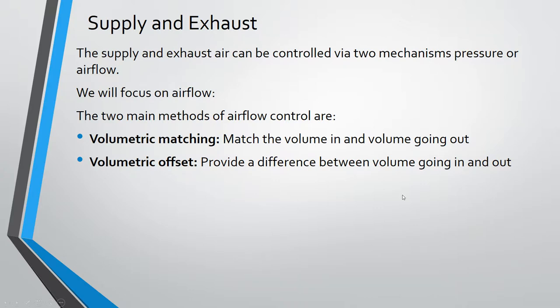Now, volumetric offset, this is done more in a pressure scenario. So you provide a difference between volume going in and the volume going out. Typically, the volume going in is more than the volume going out, which air has volume. It has mass, which then means that air going into that space starts to pressurize that space. And that's how you create a positive pressure environment. You would want to use a positive pressure environment in spaces where you don't want things to come in. Like operating rooms are typically positively pressured so you don't get contaminants coming in.